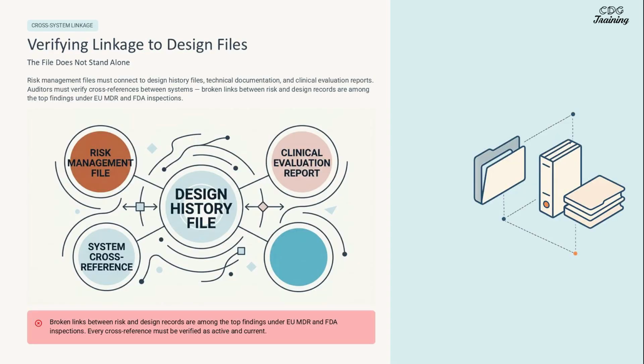Risk management files must connect to design history files and other documentation. Auditors verify these connections to ensure comprehensive risk management. Closing the lifecycle loop involves ensuring post-market surveillance data is integrated into the risk management file, signaling robust lifecycle thinking.